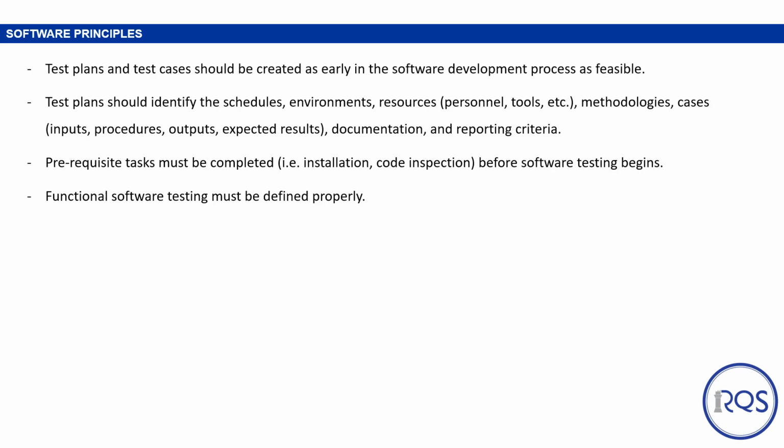Test plans and test cases should be created as early in the software development process as feasible. Test plans should identify the schedules, environments, resources, methodologies, cases, documentation, and reporting criteria. Prerequisite tasks must be completed before software testing begins, such as installation and code inspection. Functional software testing must be defined properly.